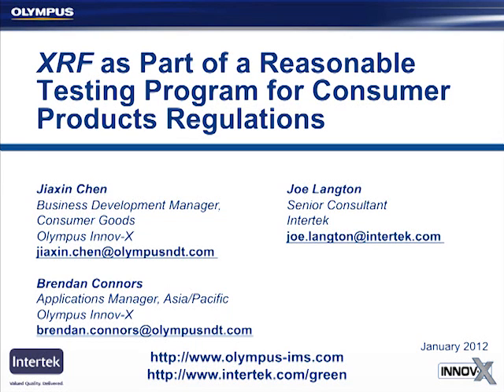I also see another question on, can we use XRF for analysis of a ceramic? And I see another one on, can we use XRF to test liquids? There are a number of sample types you can use XRF for. I've focused on plastics and metals here, but there's not really any limitation on what kind of sample you can test. Basically, as long as you can put it in front of the analyzer, you can test it. The limitation is what you're testing for. So it needs to be an application that tests for elements, and they need to be higher than the minimum detection level for an analyzer.